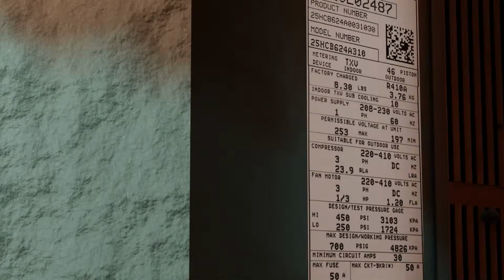Now's a good time to note the designed factory charge for the unit you're removing. That way you can know what to anticipate you're going to get out of the system in terms of refrigerant weight. Again, you may get more or less depending on if the system had a leak, if somebody overcharged it, or if it has a long line set.